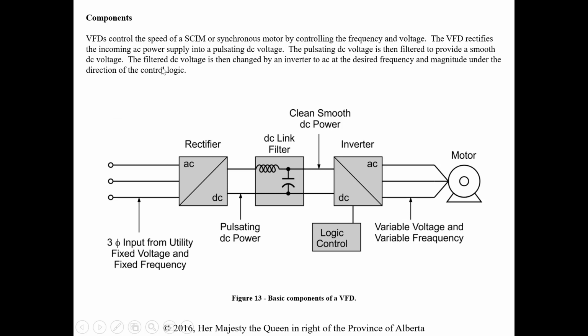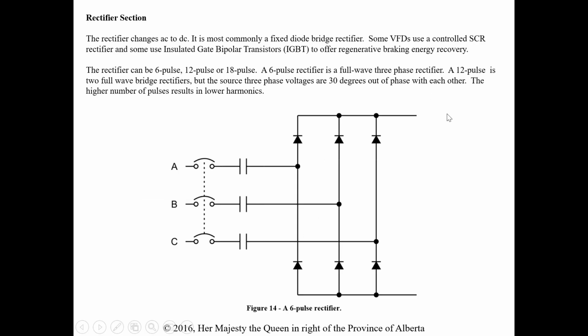So again, our components. VFDs control the speed of a SCIM or synchronous motor by controlling the frequency and voltage. The VFD rectifies the incoming AC power into a pulsating DC wave. So this is not new to us. We have our rectifier. We get pulsating DC coming out. We get filtering action here from our, this would be an L section. We have our choke and capacitor filter. Then we get our clean, smooth DC coming out into our inverter, and then we can manipulate the AC output to the motor itself. So again, very similar to UPS. We just don't have that storage option for our battery section.